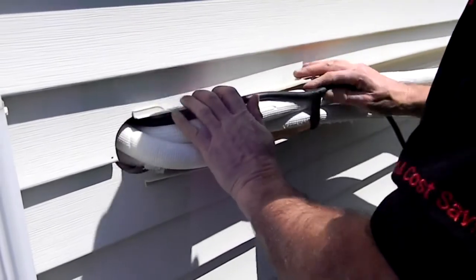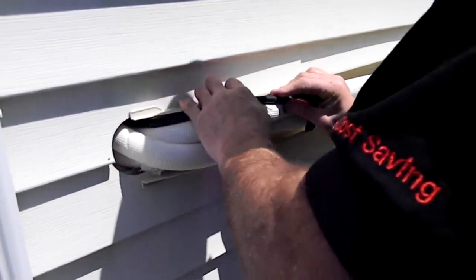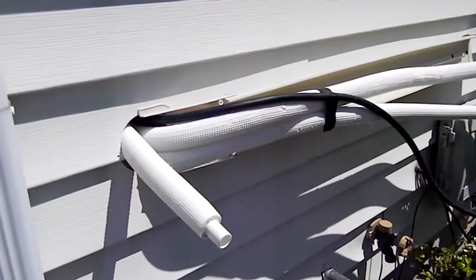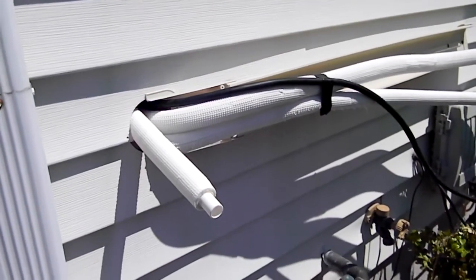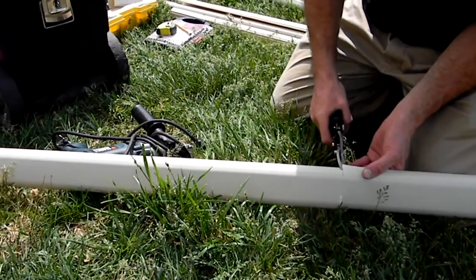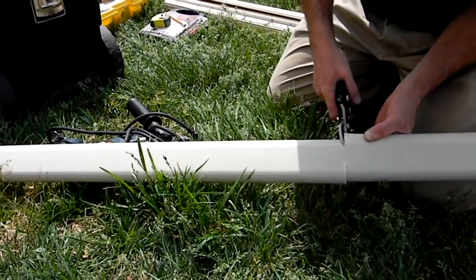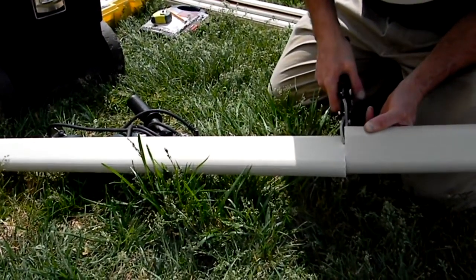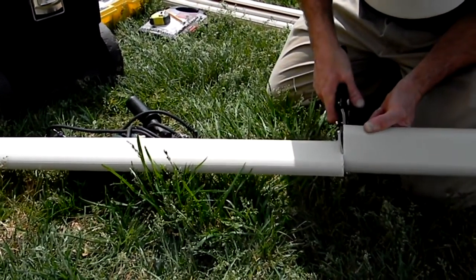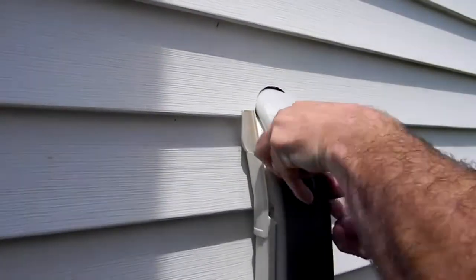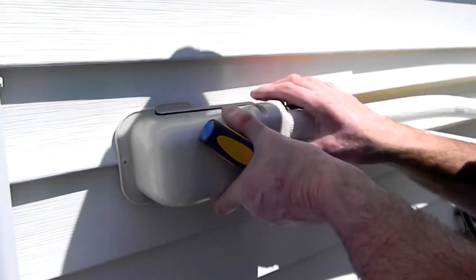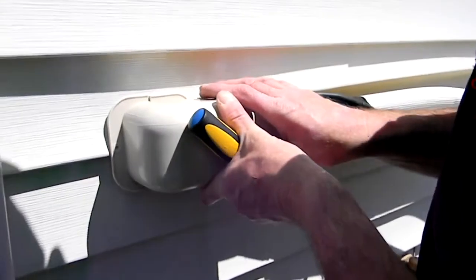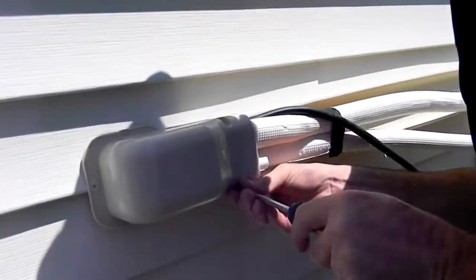We recommend using the optional line set cover to protect the tubing, prevent air and rain infiltration, and to provide a more attractive finish on the job. The line set cover can easily be cut with a pair of shears for fitting to the correct length. Fill the hole to prevent air leakage or pests from entering the building before placing the caps on the entrance elbows.